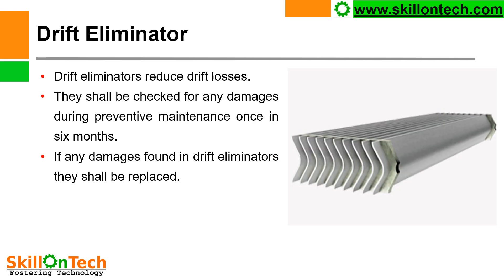Drift eliminators — here you can see these are the drift eliminators. They reduce drift losses by preventing water vapors from being carried out by the air when the induced draft fan is sucking air. They are provided on top of the PVC fills, above the distribution headers. They shall be checked for any damages during preventive maintenance once every 6 months. If any damage is found in drift eliminators, they shall be replaced.